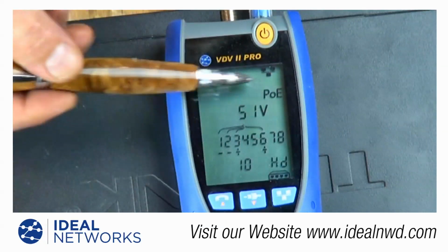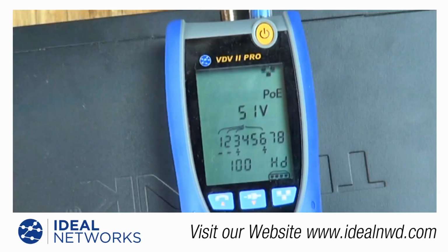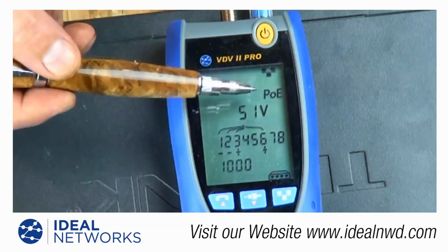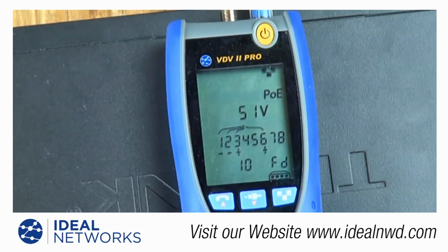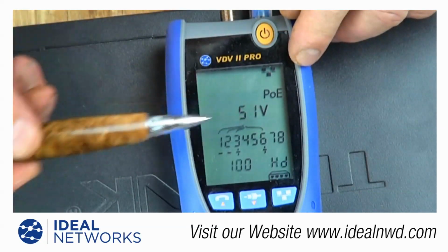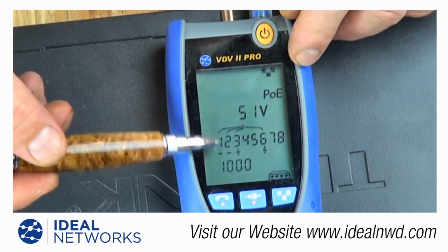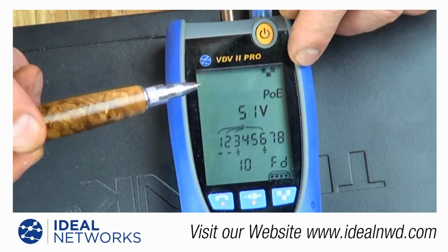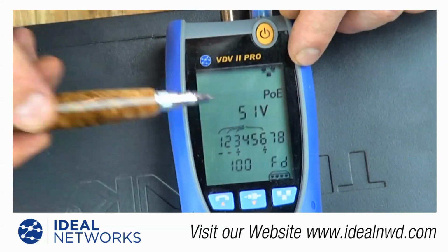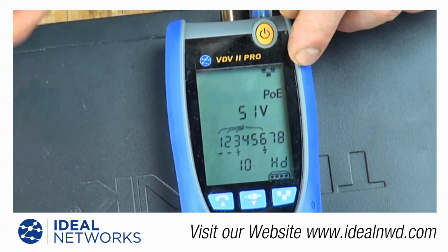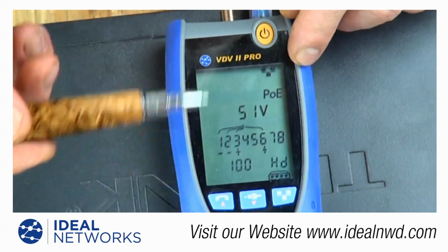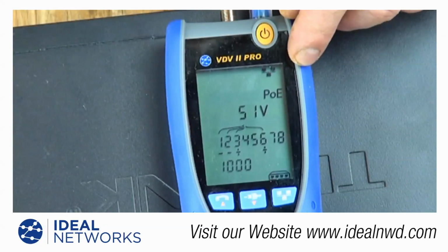It also shows the power over Ethernet available from the switch. PoE is very common today—it stands for power over Ethernet, and IP cameras, voice over IP phones, and other devices use it. It's indicating about 51 volts of power, with pins 1 and 2 as the negative side and 3 and 6 as the positive side. Keep in mind that's a DC voltage the switch is indicating, and 51 volts is within the range you'd expect from a PoE device.